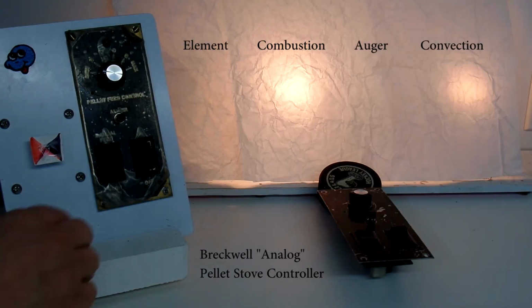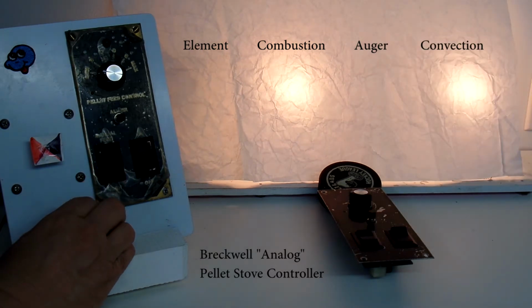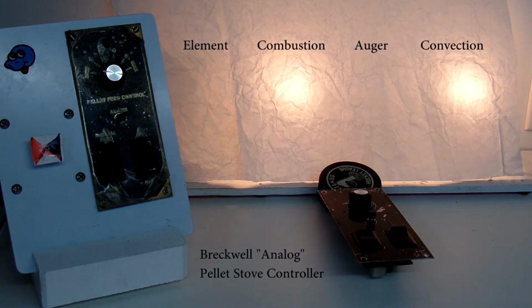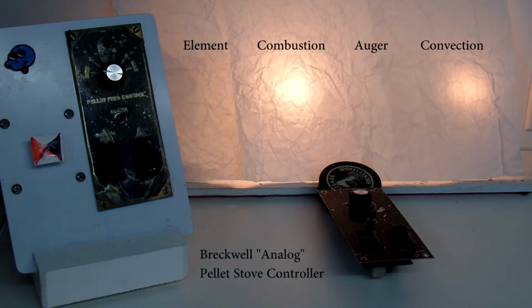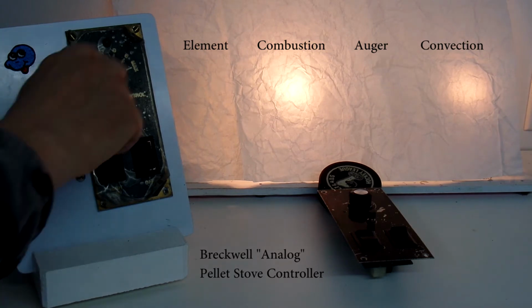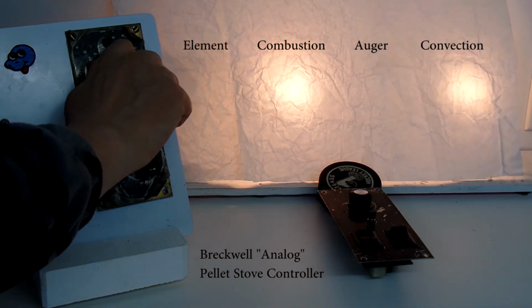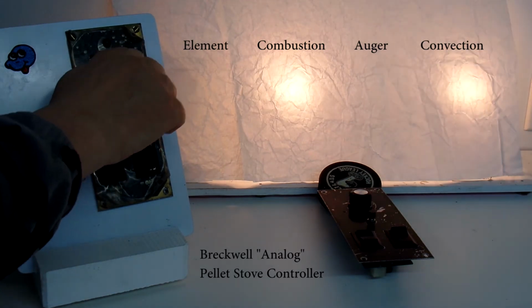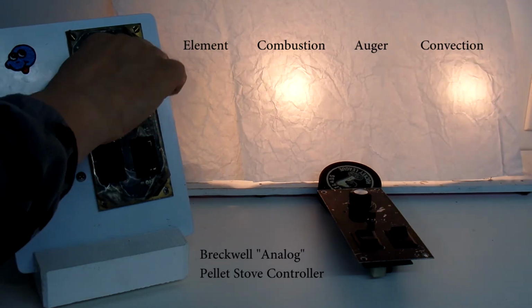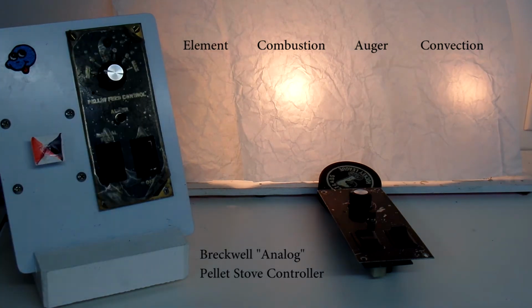The first, of course, is the manual control, where if I press the switch down here, I put it to high, and we saw the intensity of the light go high. Go back to low, high, low, high. The other thing I can check now is the manual control of the intensity of the convection or room fan. I'm currently in low, so I'll switch over to B, C, D, E, max. So we see that the intensity through low, B, C, D changes. That is functioning correctly.